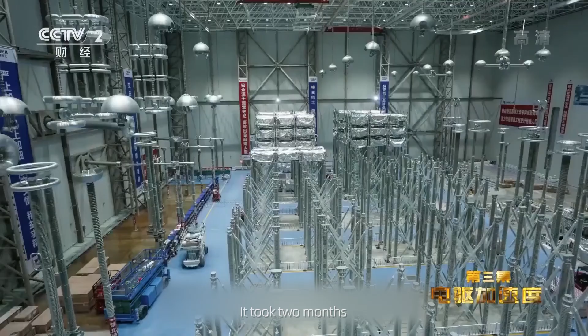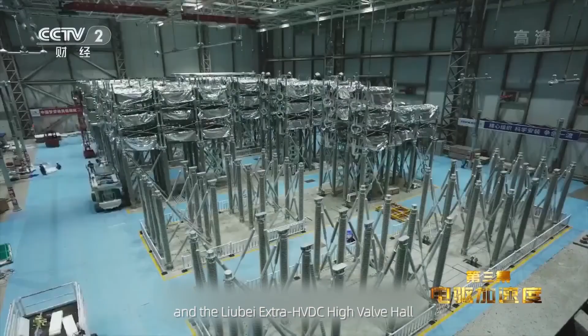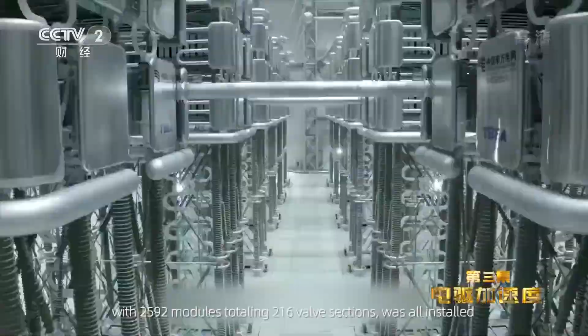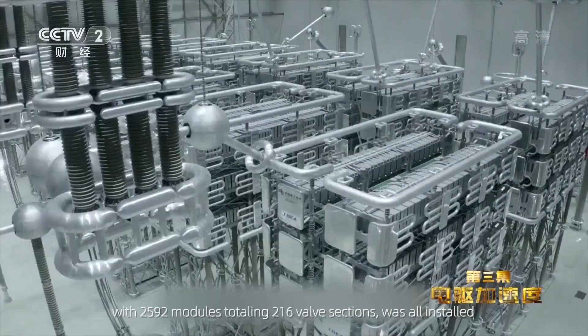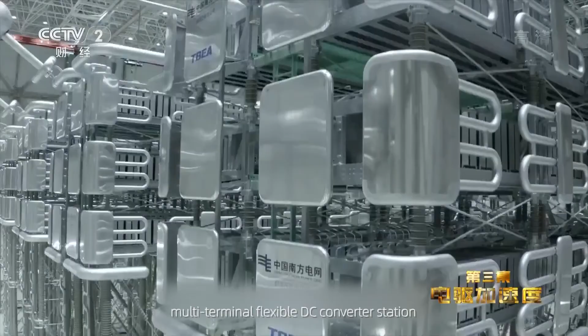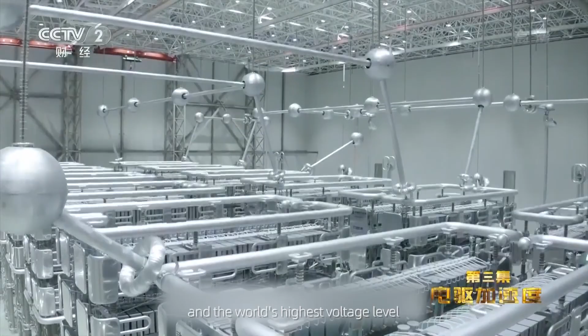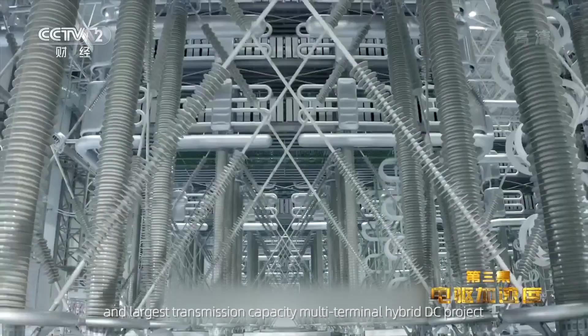It took 2 months, and the ultra HVDC valve hall with 2,592 modules totaling 216 valve sections was all installed. This is the world's first ultra-high voltage multi-terminal flexible DC converter station and the world's highest voltage level and largest transmission capacity multi-terminal hybrid DC project. Before they are officially put into operation, they must also undergo an energization test. Energization is the key moment to test whether the entire system is built and qualified.